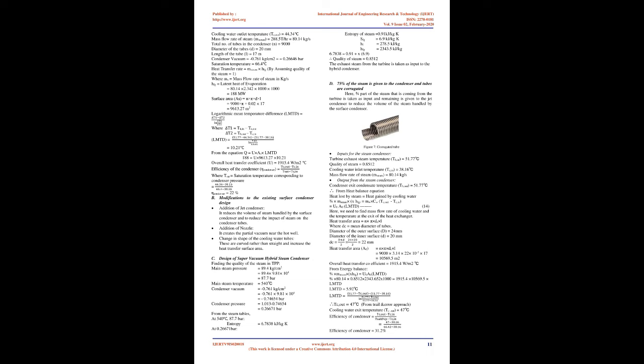The outlet cooling water should be clean, or a filter is important at the jet exit. The fluid from the blending chamber is sucked by a pump and is discharged through a nozzle as a high-velocity jet. This nozzle is united with the outlet of the condenser shell opening from where condensate is discharged to the hot well. The hot well discharge opening of the condenser shell is intended as the part of a diffuser throat where the nozzle releases high-velocity cooling water through a mixed condensate jet. This nozzle and diffuser throat position is represented in Fig. 6.